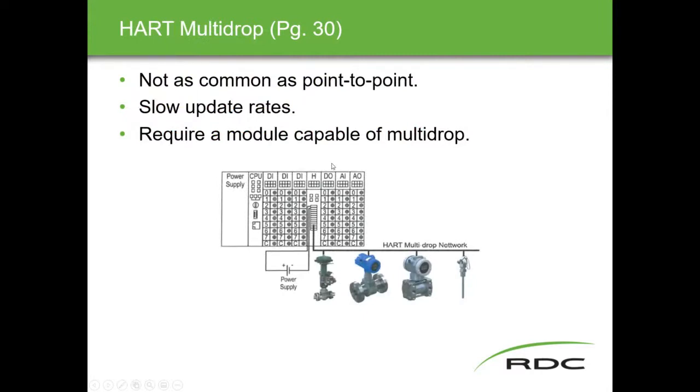Okay, multi-drop HART, this is what we're kind of building up to. Not as common as point-to-point to this day, and it probably never will be, because if we're going to get into multi-dropping, there's technologies out there that are much better at it than HART, and that's kind of why we're talking about the different ones. Multi-drop HART has slower update rates, and it requires a capable card in order to be able to do multi-drop.